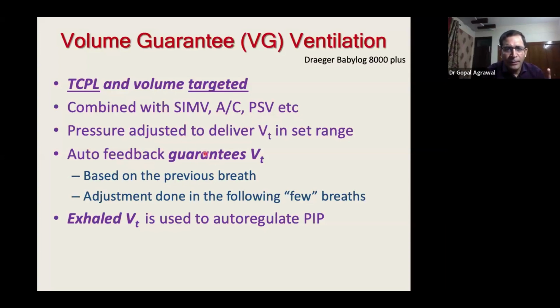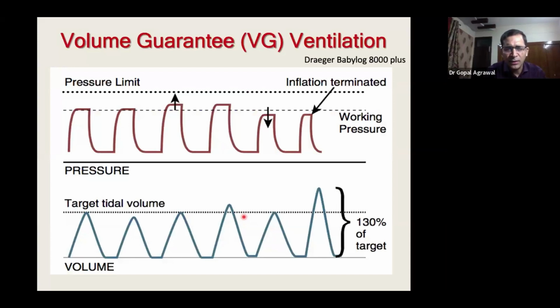And auto feedback guarantees tidal volume. The previous breath's tidal volume adjusts the next few breaths. And by default, exhaled tidal volume is used to calculate the volume guarantee, which is being delivered in the next breath. Let's see this picture. So suppose with a set pressure, the set tidal volume is delivered. This will be detected by the machine, and it will deliver the next breath with the same pressure. And we'll see with the same pressure what tidal volume is being delivered.